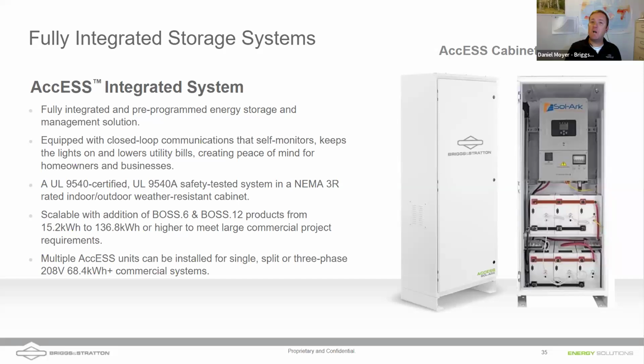I apologize for that picture of the older solar converter. But this goes back years, before the 6.6 even came out. We've been providing these AccESS cabinets, and installers still really like them. They don't want to put it in a garage or on the outside wall of the house. Instead, you get this NEMA 3R rated cabinet. Put the SolArk in, put some Amplify batteries down below, each one 3.8 kilowatt hours, and using bus bars and all the parts that come with these AccESS cabinets, put together a quick system. These can be a great solution for somebody not wanting to mount it on a wall.